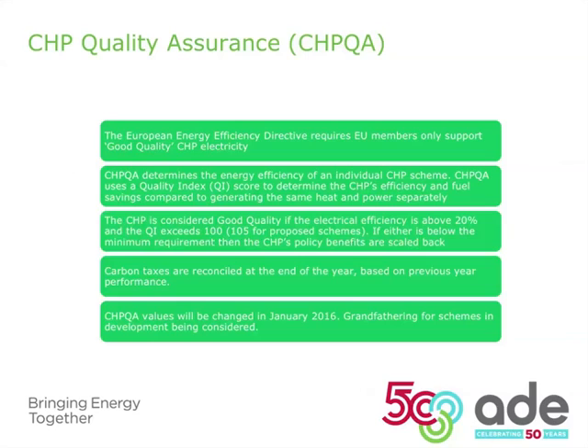It uses something called a quality index score to determine the CHP's overall efficiency and how much fuel it saves. That comparison is made against essentially what would have happened if you tried to generate that same amount of heat and power separately, so in a power station and a boiler. And then it looks at what your CHP has done and says, well, how much energy have I saved by generating efficiently, or generating in one process? And then we put that through into the quality index score.